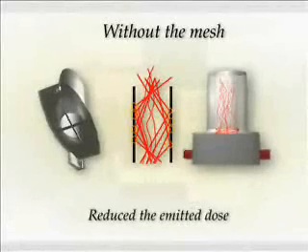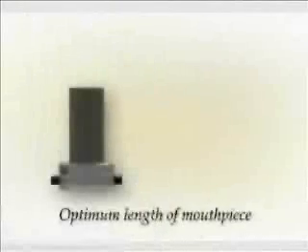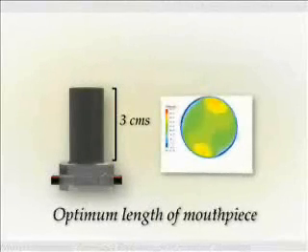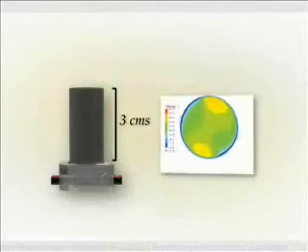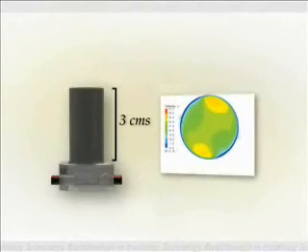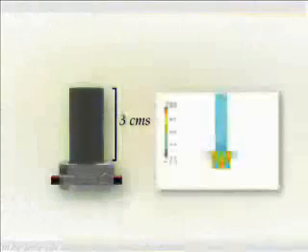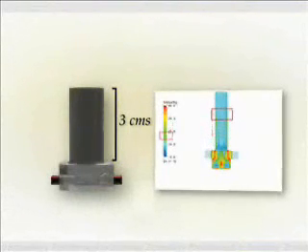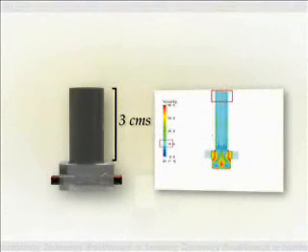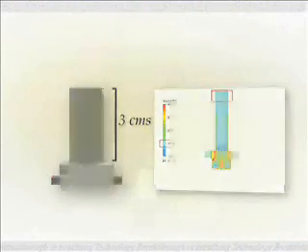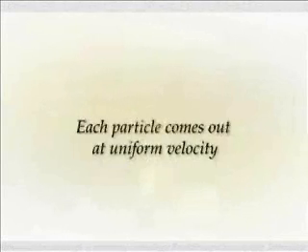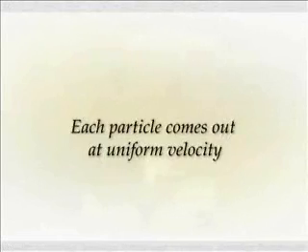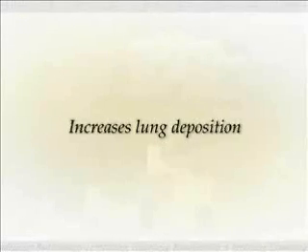The optimum length of the mouthpiece, which is 3 centimeters, creates a uniform exit velocity. As we have observed, there is a significant decrease from the chamber velocity to the entry velocity. But during the passage through the mouthpiece, there is a further reduction in the velocity, making it suitable for inhalation. Also, what is important is that each particle that comes out does so at a uniform velocity, thus increasing the lung deposition.